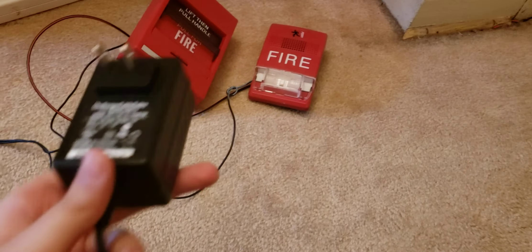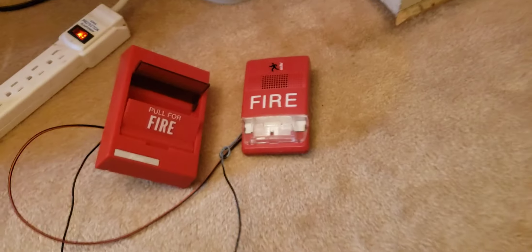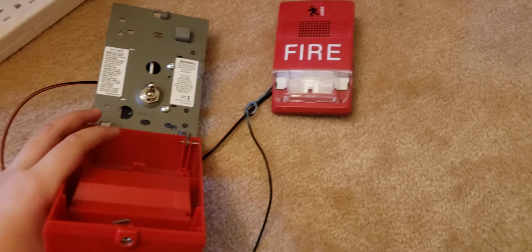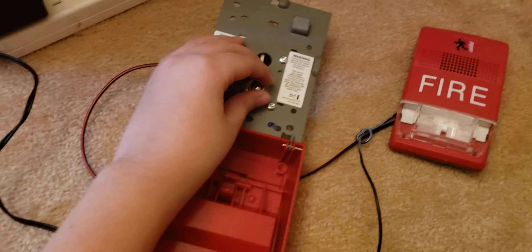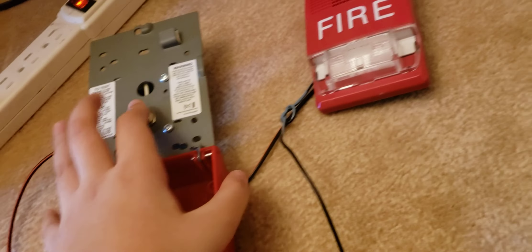I will test it so you guys can know. Before the test — with the voltage, as I already said, it depends what alarm you're using. I'm using the Genesis since it works on 12 or 9 volts. Now we'll plug this in and turn the cord on. We're going to pull it on and see if it works. You see the strobe is now flashing. That is how you wire a pull station to a fire notification appliance. Now you can see it is wired and fully working and functional.